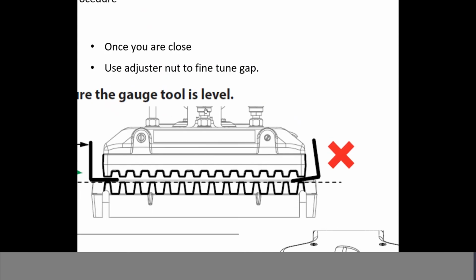On the Chick-fil-A unit, we have one in the front and one in the right rear that you can adjust. The one in the left rear is a fixed one, a floating one, if you would. It just sits there and floats. Just like all the other grills, make sure that your bottom attaching nut that goes through the cowl into the platen has no thread showing. Remember, if I have to change a thermocouple or a safety thermostat, I have to separate the platen from the cowl. In order to do that, you have those 6 bolts on each side, and then you have to remove each of the shoulder bolts to adjust it in order to separate it.